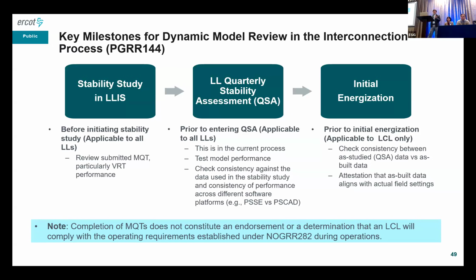We can put as many model checking points in the interconnection process, but we believe these three model checking points are good enough. The whole point of doing this is to help our large load customers and our TSPs maintain the model data and model performance throughout the interconnection process. One thing I want to point out is this model quality test review. The primary purpose is to ensure they are in good shape to move on to the next step in the interconnection process. This is the minimum test and review, and it does not guarantee, nor does ERCOT endorse, that they will meet these requirements in real-time operations. It's their responsibility to meet the operating requirements.